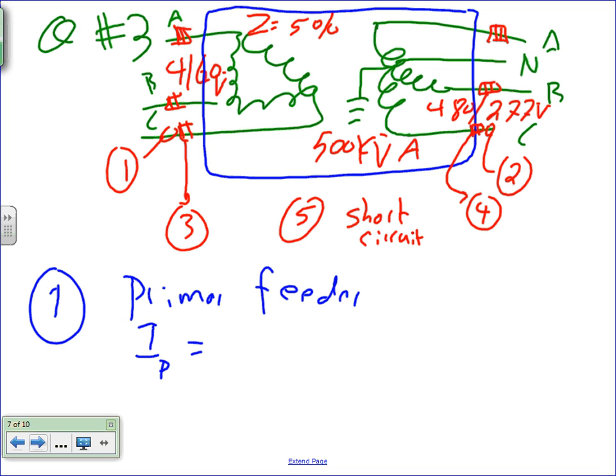Number one, the primary feeder. Number two, the secondary feeder. Number three, the primary fuse. Number four, the secondary fuse. Number five, the short circuit. Okay? Everybody knows what we need to size for this transformer? We need to size the feeders on the primary and the secondary, and the fuses on the primary and the secondary, as well as the short circuit. Any comments about the given? Anything that you want me to read for you?